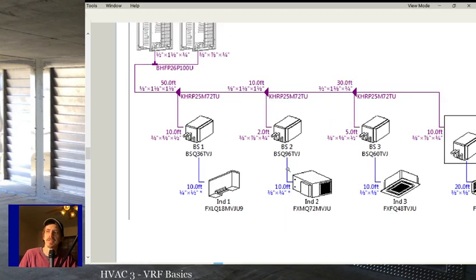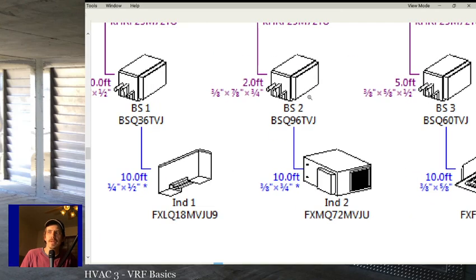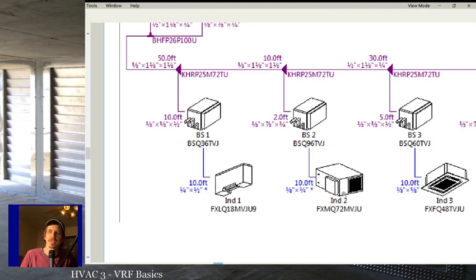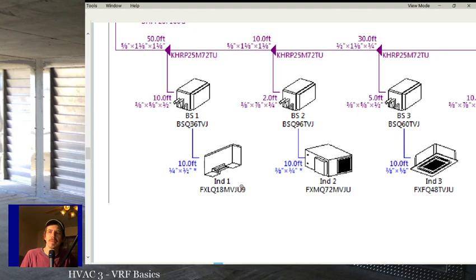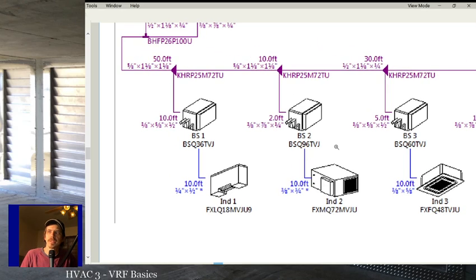There are instances in which it does help to run the line a little bit farther and go around, but those are pretty rare. That's usually just to try and keep the line the same size. If it's written down as 10 feet, but you could really do it in 5, then maybe try and run it just a little bit longer so you don't have to double check it. But rarely does this size change if you're going to a single unit. No matter what you do, it's usually going to be the same size from the branch selector to the units. It's these long runs that can be kind of weird.